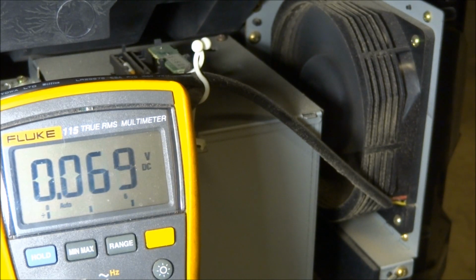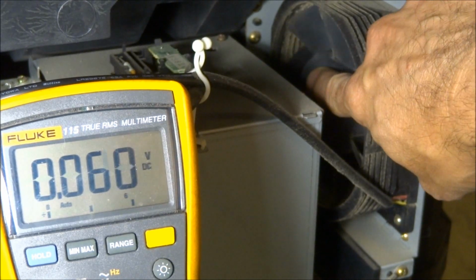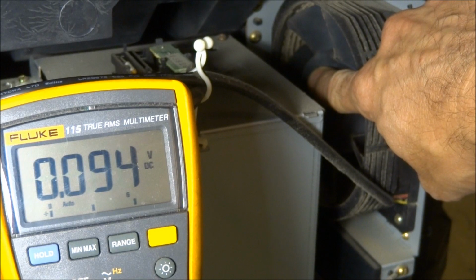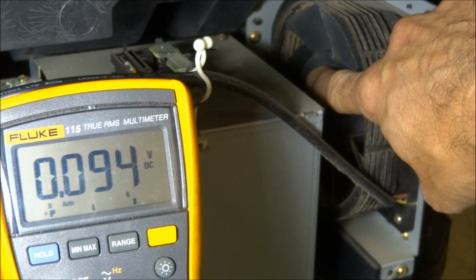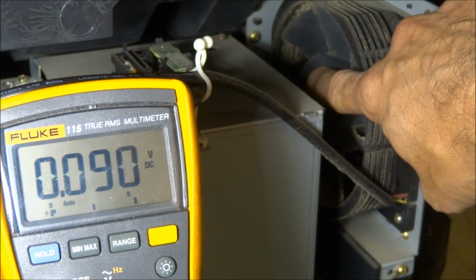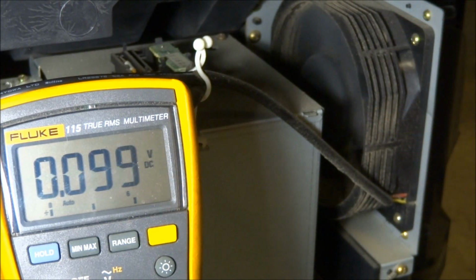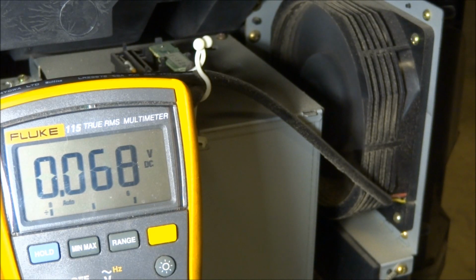But back on the sense lead, you can see the voltage is continuing to jump. Right now it's steadied out, so the set will probably run okay from this point on. But the problem is that fan definitely needs to be replaced. If I reach in and stop the fan, after it senses it stopped for a moment, it should, if the fan's working correctly, send a high. Oh, and it's not—so definitely we've got a problem. Oh, there it goes—okay, it sent a high. Took a second, sent 4 volts back to the sense lead indicating there was a problem with the fan. So we want to look at replacing that fan to repair this one.